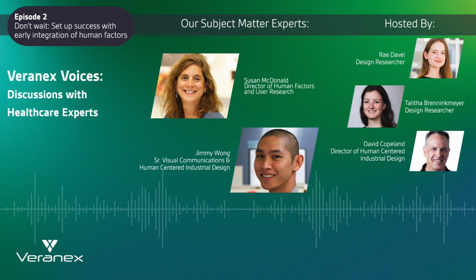So for example, if you're designing something in a surgical space that's using radiation, you need to understand your user is going to be wearing a lead vest and likely eye protection and/or gloves. But also lighting could be different. Maybe the room is dim. Maybe there's a loud hum from an MRI machine. So if you're providing audible feedback, you need to take that into account, and also visual feedback in different lighting conditions.